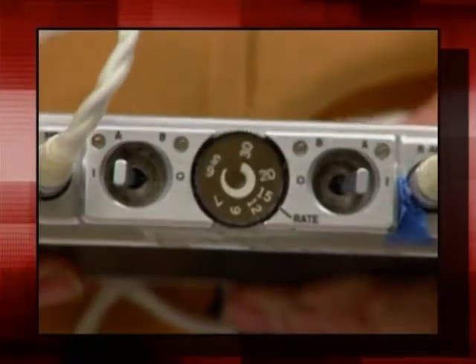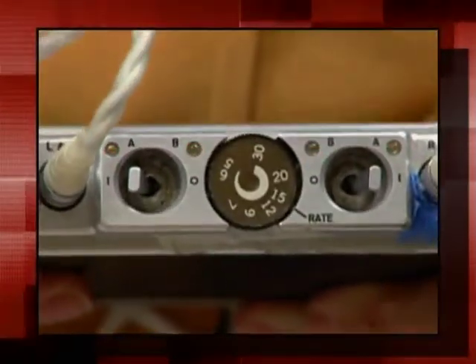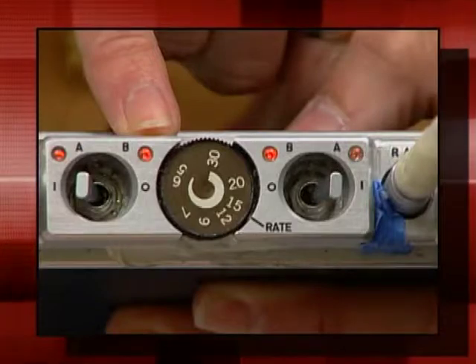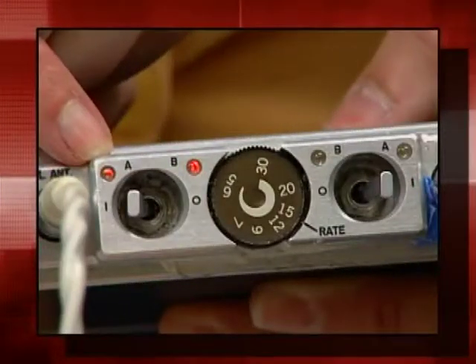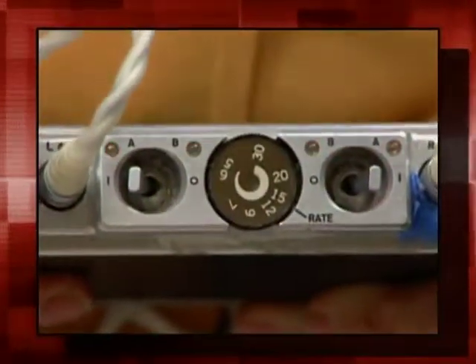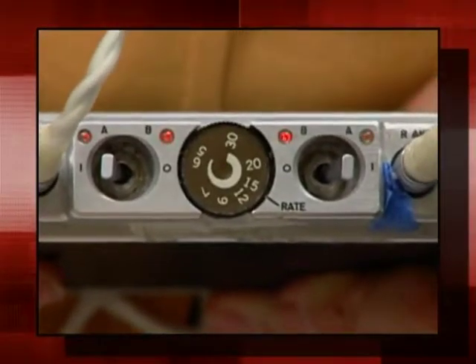So we have our transmitter. We've replaced the battery now. So we have fresh batteries. Everything should be fine if that's the problem. You can tell if your battery is working because when the transmitters are on, you just click the button. There are two flashing buttons that you should be looking for. One is identified B for battery. The other is A for antenna. They are both flashing. If you replace the battery and you're still having a problem with the battery light not flashing, it tells you then that you probably have a problem with the battery connector.